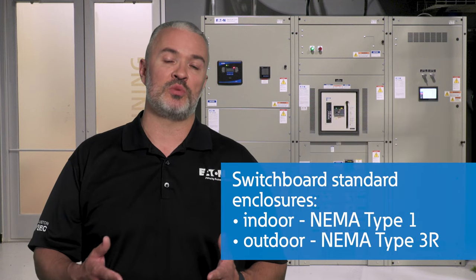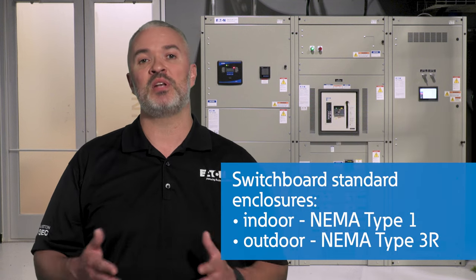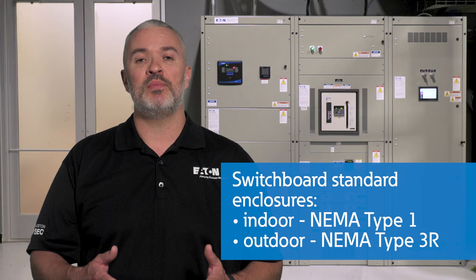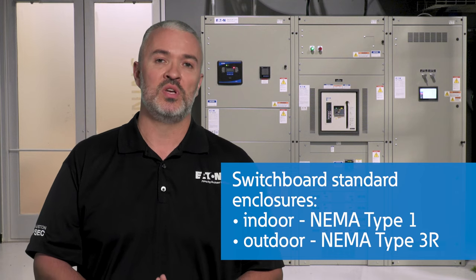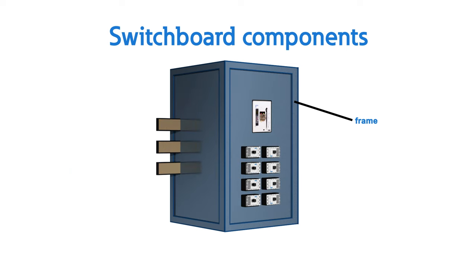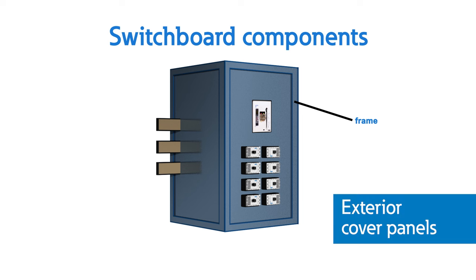Standard enclosures for switchboards include NEMA Type 1 for indoor and NEMA Type 3R for outdoor uses. After equipment installation, the frame is enclosed with the exterior cover panels. Like the dead front of a panel board, these covers allow for access to protective devices while sealing off the bus and wiring from accidental contact.